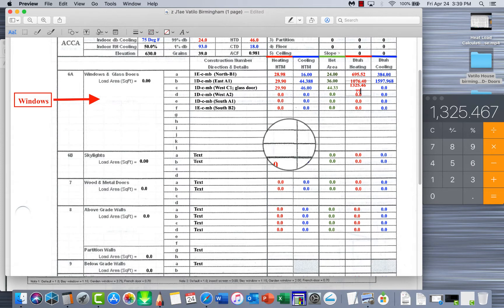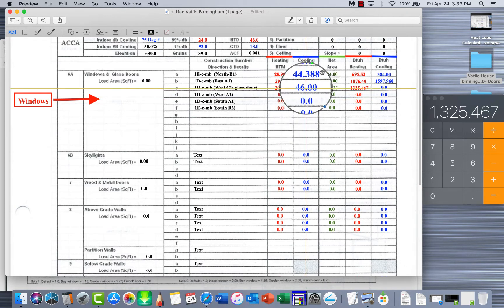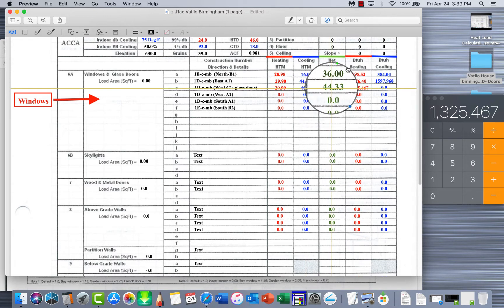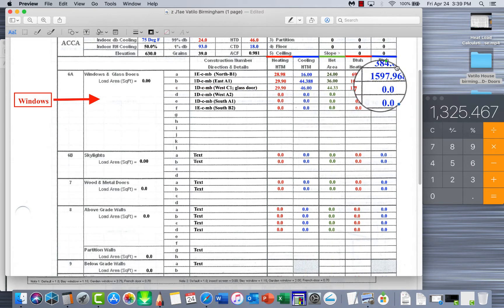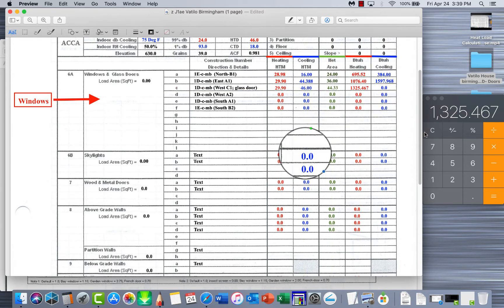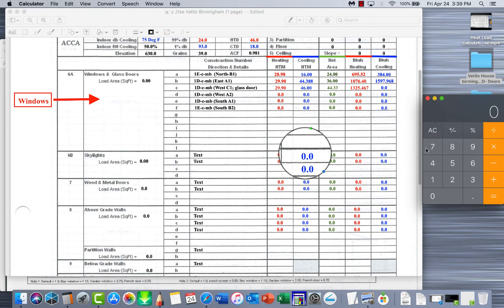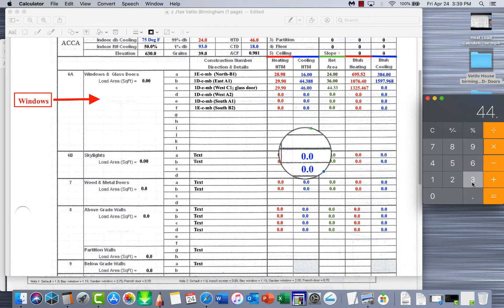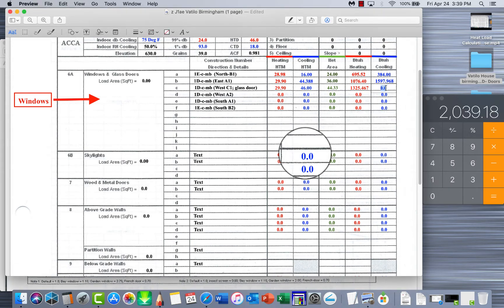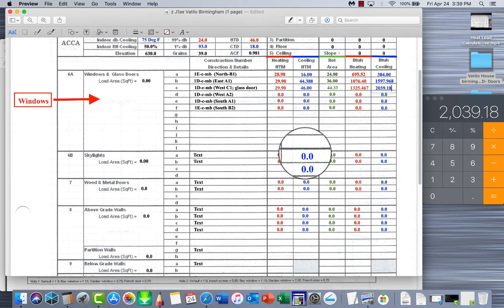So 29.90 times 44.33 equals 1325.467. Too many sevens there, there we go. Now we're going to do the same for the cooling. Cooling HTM times the square footage to give us the cooling BTUs.